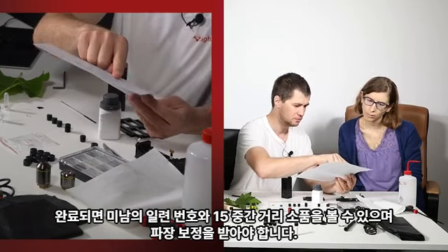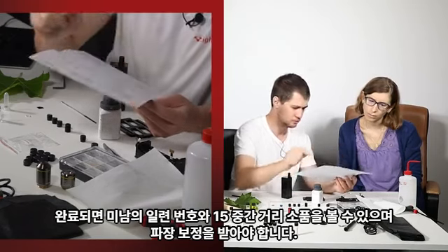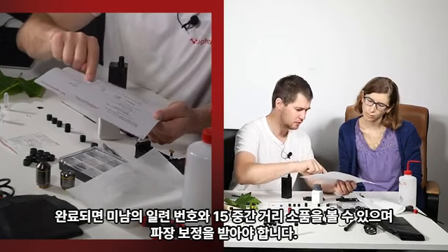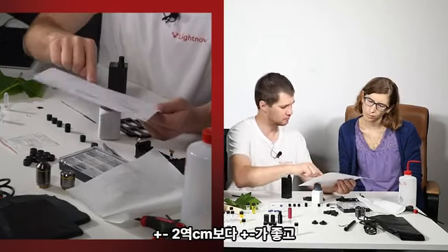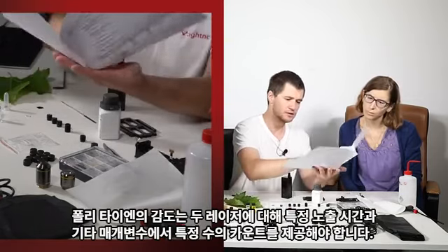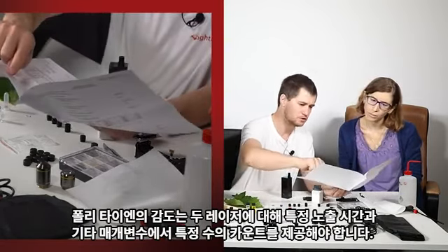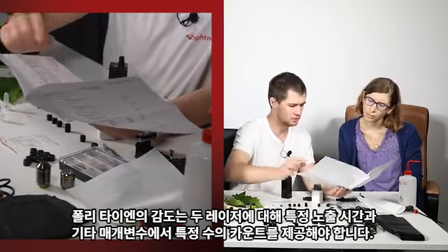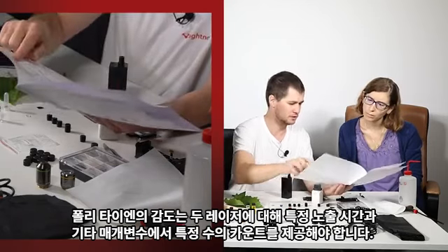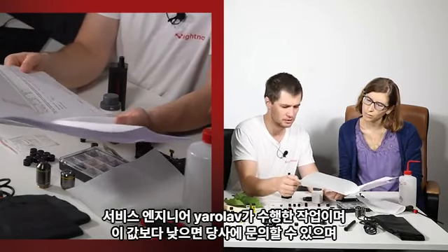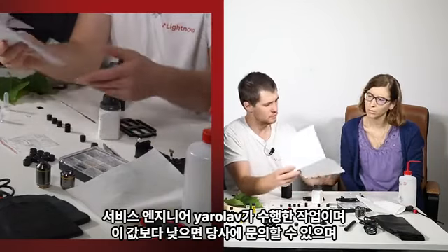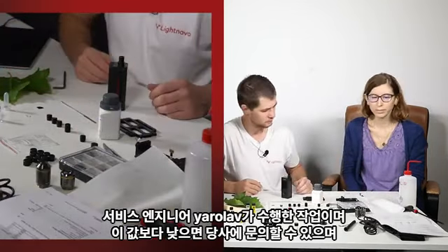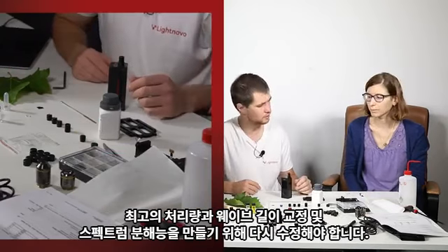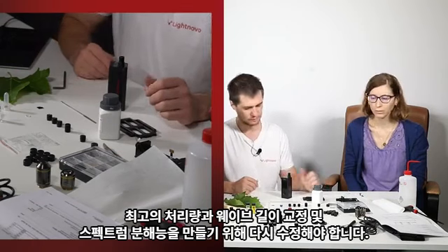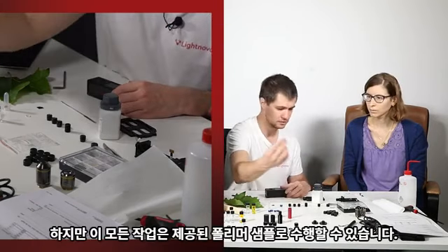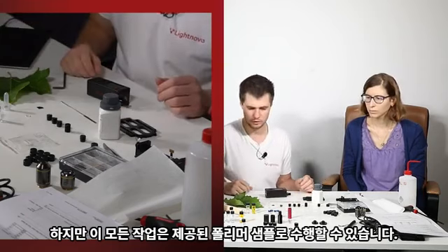You can see the serial number of the miniRaman and the middle distance probe, and you should get wavelength calibration better than plus or minus 2 inverse centimeters, and the sensitivity of polystyrene should provide a certain number of counts at a certain exposure time and other parameters for both lasers. So it was done by our service engineer, and if it's below these values, you can contact us and we will fix it to restore the best throughput, wavelength calibration and spectral resolution. But all of that you can do with the supplied polystyrene sample.